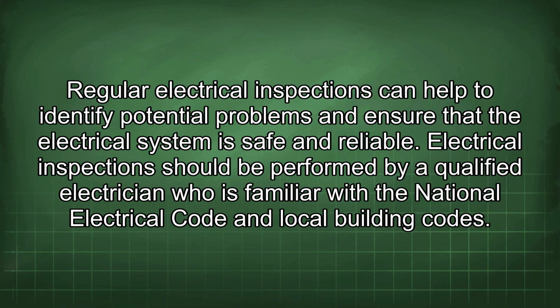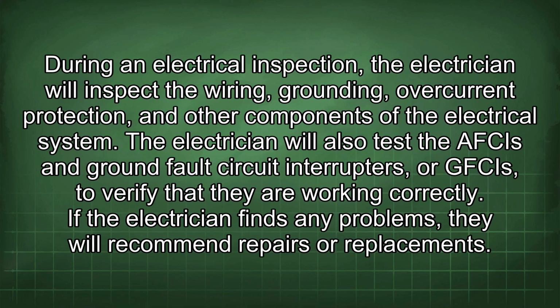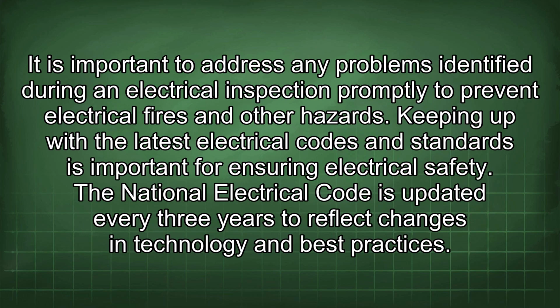Regular electrical inspections can help identify potential problems and ensure that the electrical system is safe and reliable. Inspections should be performed by a qualified electrician familiar with the National Electrical Code and local building codes. During an inspection, the electrician will inspect the wiring, grounding, overcurrent protection, and other components, and will test AFCIs and ground fault circuit interrupters, or GFCIs, to verify they are working correctly. If problems are found, the electrician will recommend repairs or replacements. It is important to address any problems promptly to prevent electrical fires and other hazards.